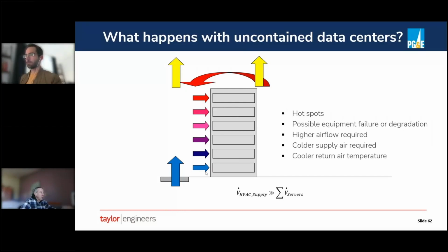Typically the servers at the bottom of the rack were usually okay because they were getting very close, sort of coupled air right out of the floor, but the space was largely mixed up, and the servers often, instead of pulling the cold air coming out of the floor, were pulling air from the hot aisles back into the servers.